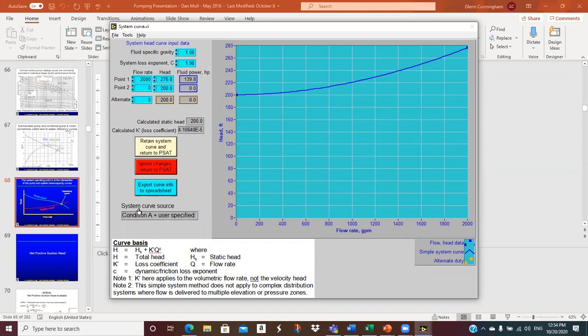And so what you do, specific gravity, you put in here. The exponent, and this system curve will be of the form, and we got some more slides on this, a total head H is equal to a static head, a static elevation. If we're picking water up down here, carrying it up to the top of the hill, that's a static head. I think we've talked about that before. And that's equal to this constant, K prime, times flow, Q, GPM, raised to a power, C, okay?